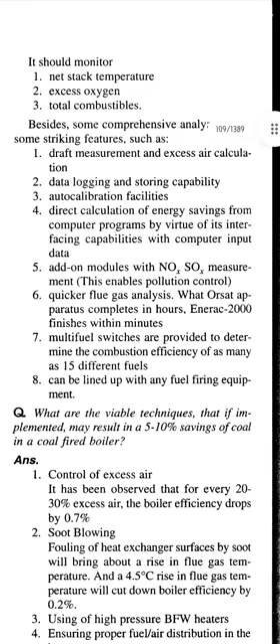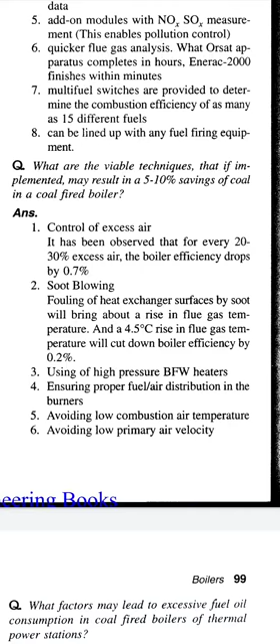Question. What are the various techniques that, if implemented, may result in a 5 to 10% saving of coal in a coal-fired boiler? Answer. Control of excess air. It has been observed that for every 20 to 30% excess air, the boiler efficiency drops by 0.7%. Soot blowing. Fouling of heat exchanger surfaces by soot will bring about a rise in flue gas temperature, and a 4.5 degrees Celsius rise in flue gas temperature will cut down boiler efficiency by 0.2%.